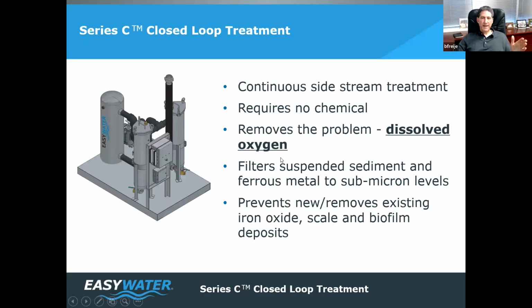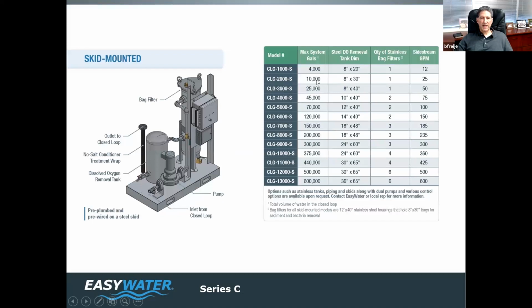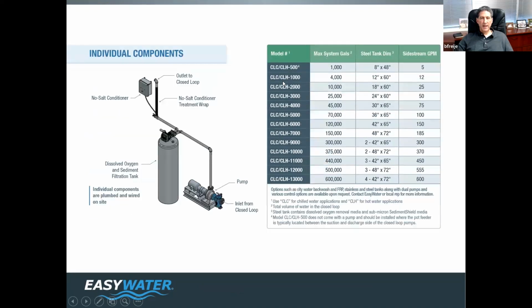So we looked at this 20-some years ago and said, let's go after the problem, dissolved oxygen. Series C is a side stream closed loop treatment system, pulls from the main header, has its own pump. First, the water gets filtered, then it goes into this tank that contains our dissolved oxygen removal media. That's the key. Minimize the corrosion by getting rid of the dissolved oxygen. Leaves there, goes through the no salt conditioner treatment to get rid of any deposits and keep new deposits from forming, and then back into the closed loop. It's simply sized by volume of water in the system. 8,000 gallons in the system, a CLG 2000S. How do you know this thing works?